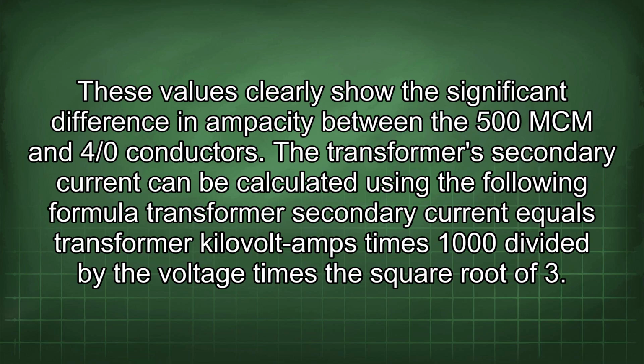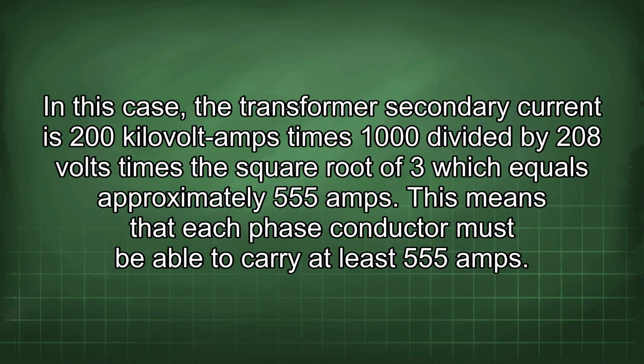The transformer's secondary current can be calculated using the following formula. Transformer secondary current equals transformer kilovolt-amps times 1000 divided by the voltage times the square root of 3. In this case, the transformer secondary current is 200 kilovolt-amps times 1000 divided by 208 volts times the square root of 3, which equals approximately 555 amps. This means that each phase conductor must be able to carry at least 555 amps.